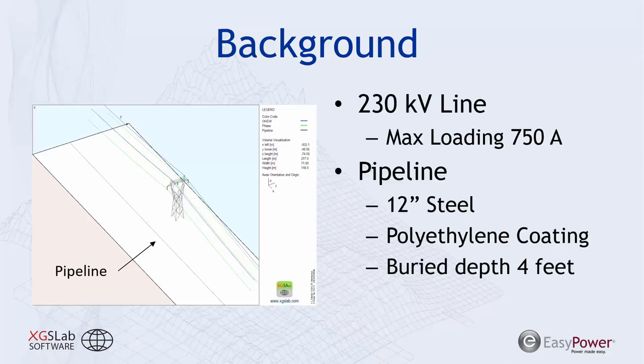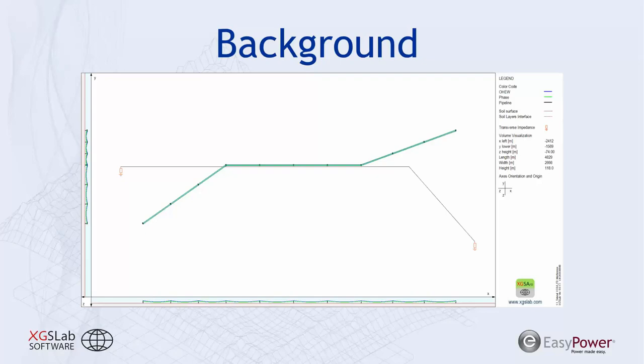And the exposure length of this transmission line on the pipeline is approximately 1 mile, where we're directly parallel. And we will have some effects as the transmission line crosses over the pipeline and then departs away from the pipeline.